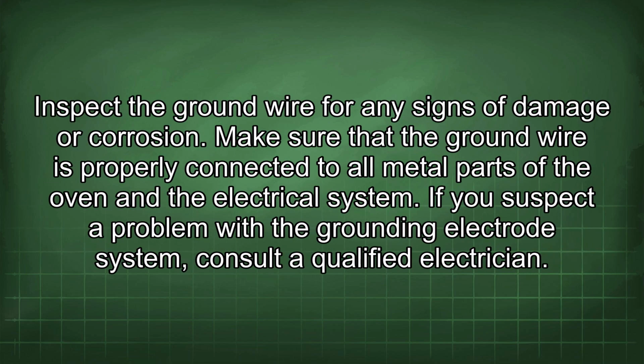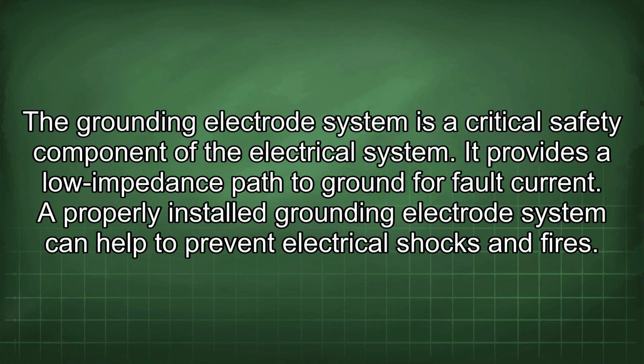Inspect the ground wire for any signs of damage or corrosion. Make sure that the ground wire is properly connected to all metal parts of the oven and the electrical system. If you suspect a problem with the grounding electrode system, consult a qualified electrician. The grounding electrode system is a critical safety component of the electrical system. It provides a low impedance path to ground for fault current. A properly installed grounding electrode system can help to prevent electrical shocks and fires.